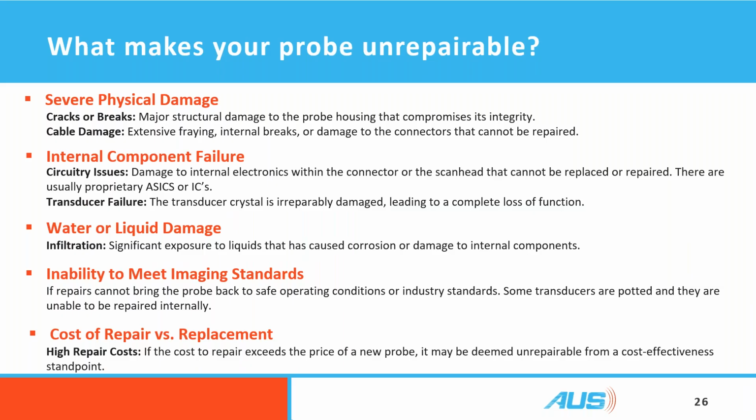Water or liquid damage can cause severe problems with the probe. Inability to meet imaging standards can point directly towards an array. And if the array is damaged, that's not repairable. We have to get a completely new array, which means that's the cost of a brand new probe. So they're not considered repairable.